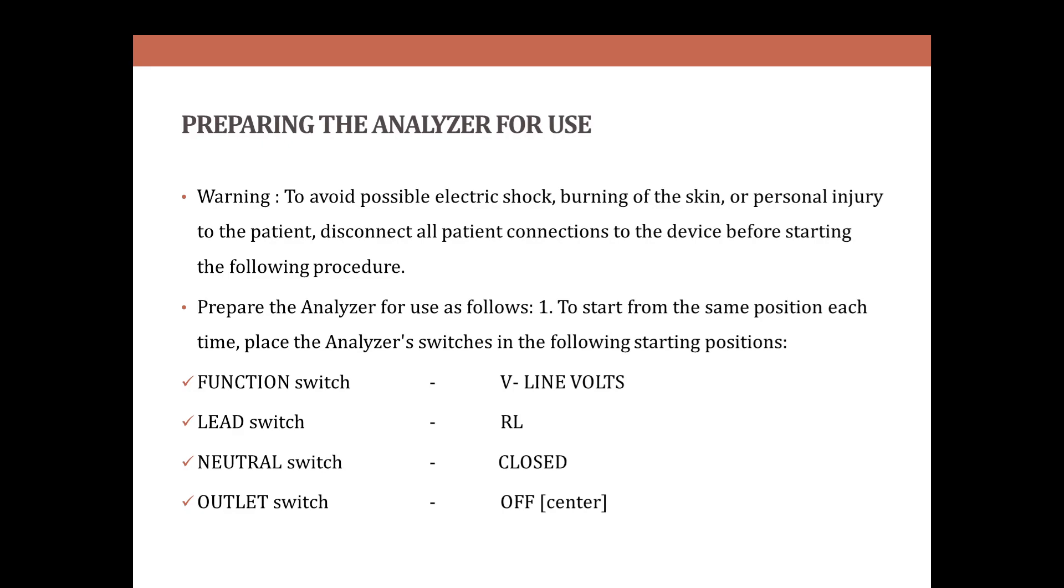You should prepare the analyzer for use as follows. First, start from the same position each time and place the analyzer switches in the following starting positions: function switch in the V-line volts, lead switch in the RL, neutral switch should be closed, and outlet switch should be off.